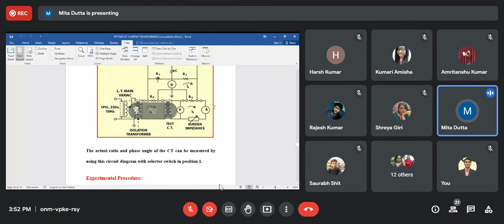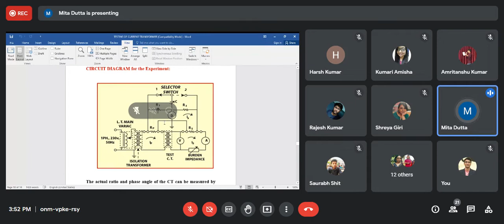And we are going to find out ratio and phase angle, and we are performing 3 runs. In run 1, we will test the CT at rated voltage and rated current. That means now, since we are using here 10 ampere by 5 ampere CT, so the nominal ratio will be 2:1, and the burden on CT is 20 VA, and this is the rated burden. This 10 ampere and 5 ampere, this ratio and this burden, it is being written on the nameplate of the test CT.